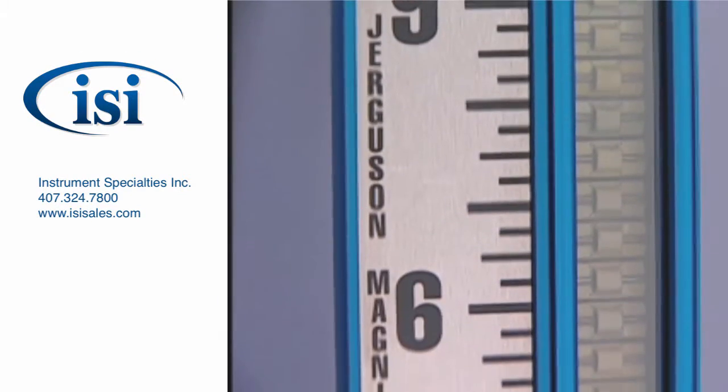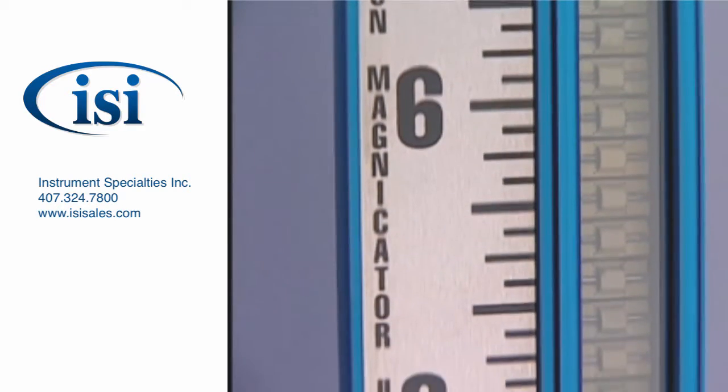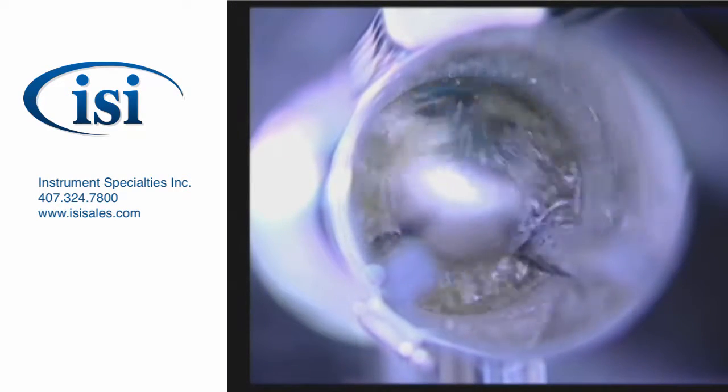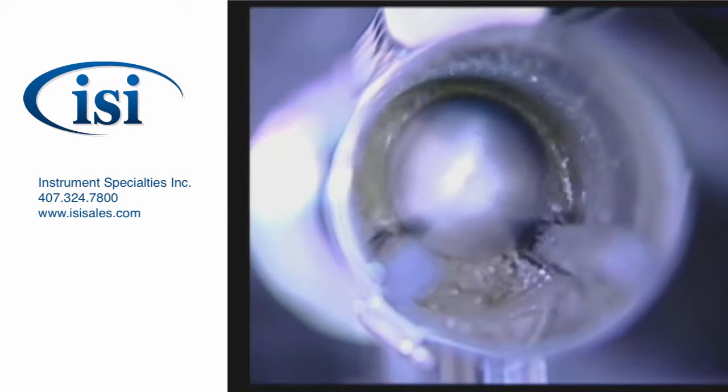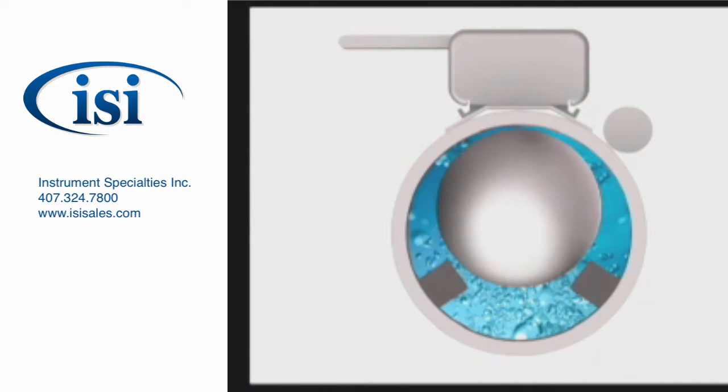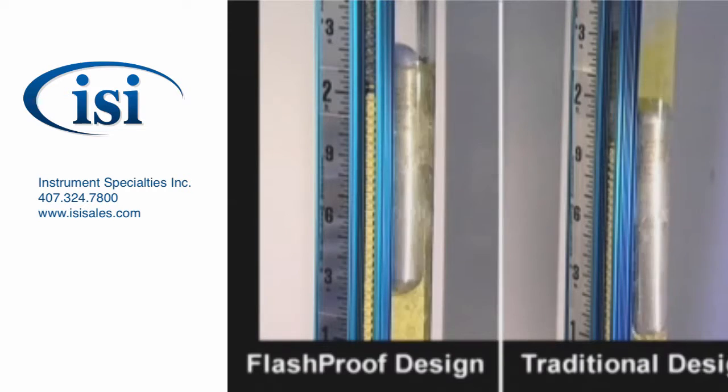The new Jerguson Magnicator FlashProof Gauge features a unique chamber design to eliminate problems from boiling liquids and flashing vapors. By employing an oversized 3-inch Schedule 40 chamber with internal guide rods, entrained gases easily escape past the float.